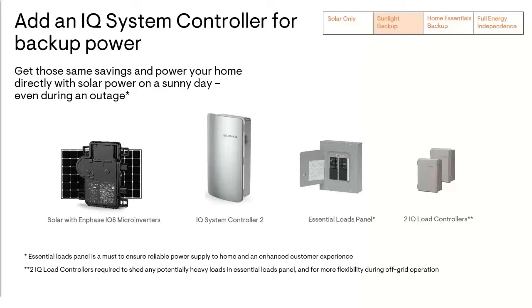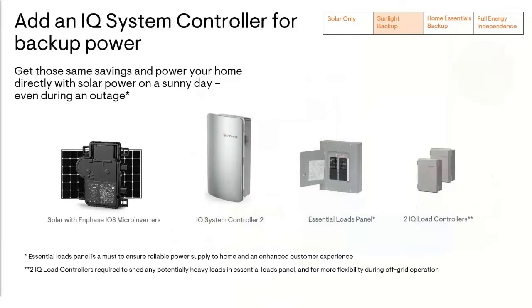The revolutionary feature of the IQ8 microinverter is that it can provide backup power to a home while the sun is shining, and it can even do this without a battery. With the addition of the Enphase IQ System Controller 2, the sunlight backup system can disconnect instantly from the grid during a power outage, and the solar system with the IQ8 microinverter will power the home. Since the sun is the power source and is naturally highly variable, a sunlight backup system needs to be designed with this variability of power output in mind.